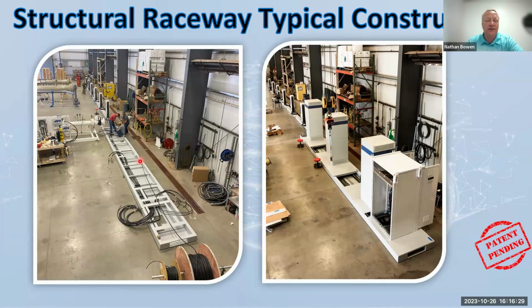a behind the fence drayage truck application. In this application, it had three 180 kilowatt Heliox Flex 180s, basically a total of 9 dispensers, a 2000 amp panel board. But you can see all the cabling is encapsulated inside of our structural raceway system. So everything is pre-wired. We actually pre-commissioned this system prior to its departure, which in this case required multiple vehicles because this system is a dynamic charging system. So you have to have a minimum of 3 vehicles to check out each system to make sure all the software side of this is working.